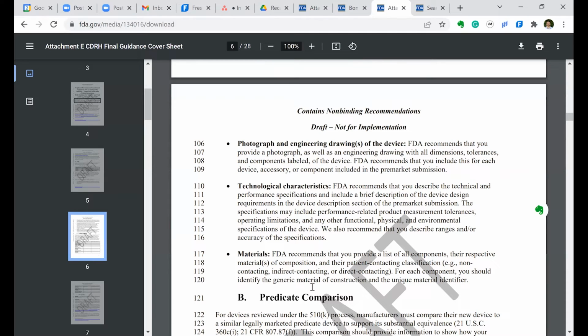We looked at three different special controls guidance documents. They look different, all three of them, but it gives you a flavor of what you can expect the FDA to want. And there's one more category that I haven't covered yet, and that's software as a medical device. And oh yes, they want a lot of detail there too. It's not enough just to say this is software as a medical device, it's used on a mobile app, and here's what it does. No, they want a lot more for software. So let me show you what you have there.